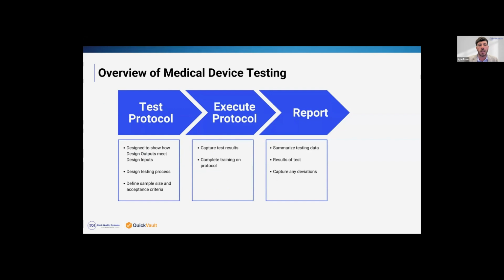So this is kind of the basic framework for how you would complete the testing. So you're going to first create a test protocol. So this is identifying what specific inputs and outputs you're testing. You're going to identify specifically the design testing process. So how you're going to test this device. Is it simulated use? Is it some external lab testing? Is it some benchtop testing you're doing, or potentially some analytical testing? All of those things can be considered part of this verification testing scope.